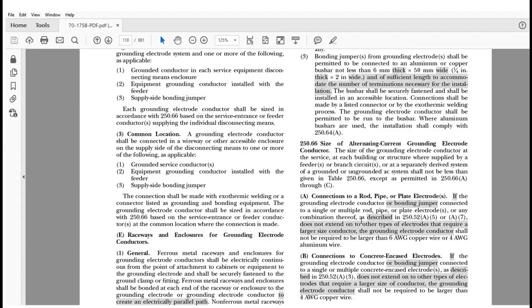I think it's important to understand that a 4 AWG aluminum wire can be used as long as you follow the rules in the code, which say that it can't be terminated within 18 inches of the earth, unless there is an actual listed device or fitting that can adequately accept that type of connection and it's listed for that, and that's a whole other topic. But it still can be done, and we still can use aluminum wire for that application. Running through the structure, no problem at all.